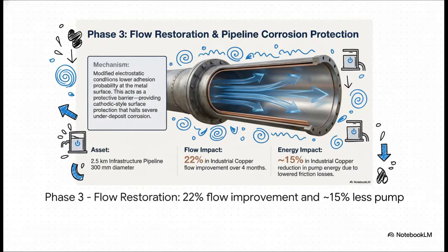But the benefits didn't even stop at the chiller. In Phase 3, they looked at the plant's huge pipeline network. As the system cleaned the pipes from the inside out, their flow improved by 22%, which in turn led to a roughly 15% reduction in the energy needed just to pump water around the plant.